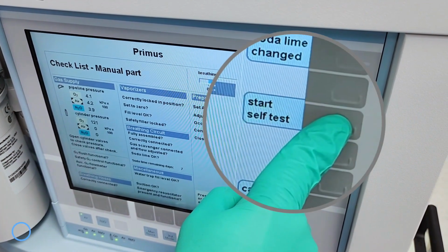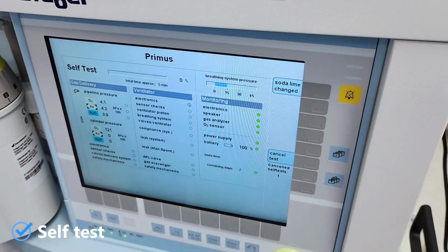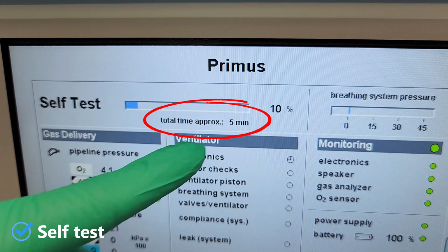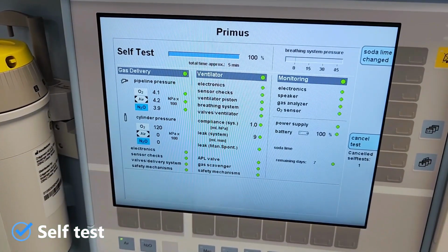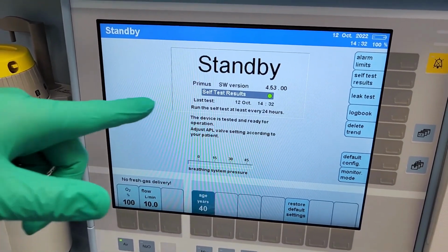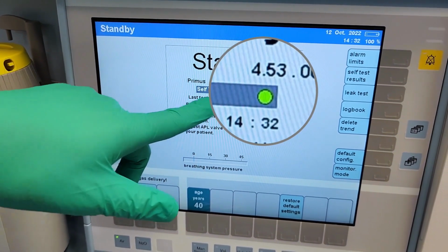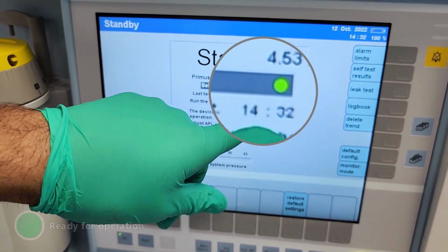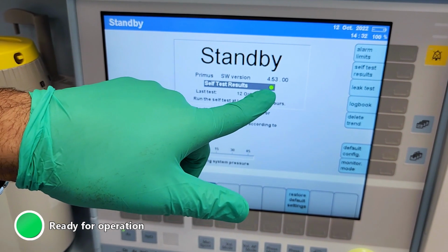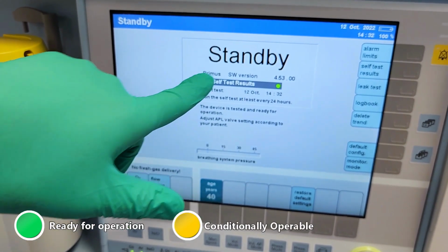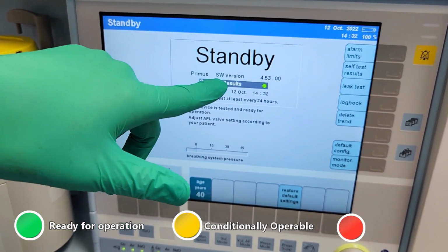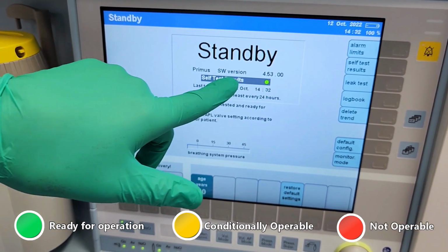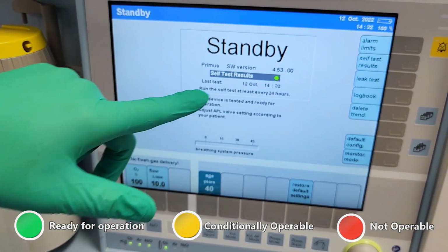Once you have completed the manual checklist, press the Start Self-Test button. The self-test will take around 5 minutes. Once the self-test is completed, the machine automatically goes to standby mode. The green color here indicates that the machine is fully operable. If it is yellow, the machine is conditionally operable. And if it is red, don't use it. The machine should be sent to biomedical.